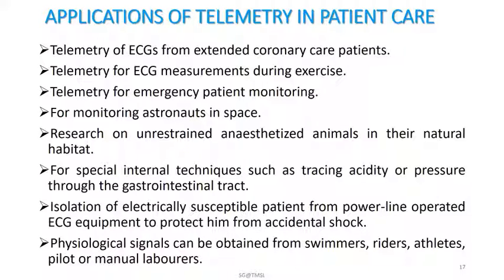The batteries are also included in the transmitter package. The area in which the patient is allowed to move must be limited because the location of the patient cannot be identified. If the patient moves beyond the range of the system, his ECG cannot be monitored.